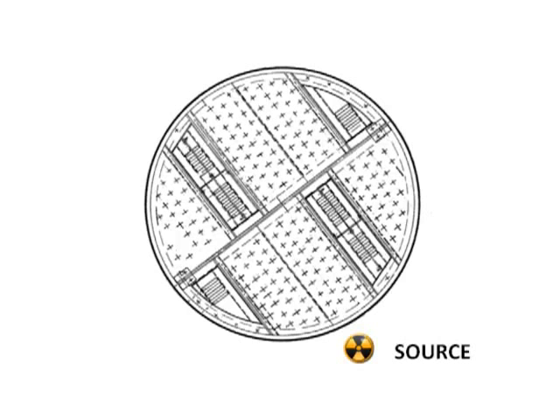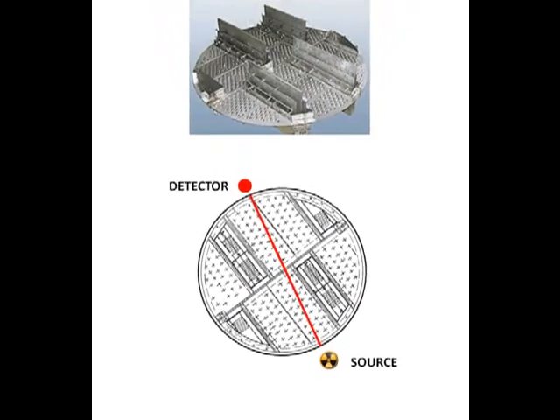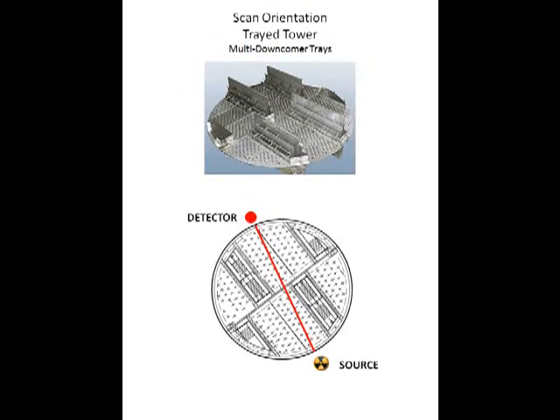In this case, the source and detector were positioned so that a gamma scan path was possible in between the downcomers. The tower scan was conducted to determine possible causes for an increased pressure drop across the tower, which forced operations to run at reduced rates.